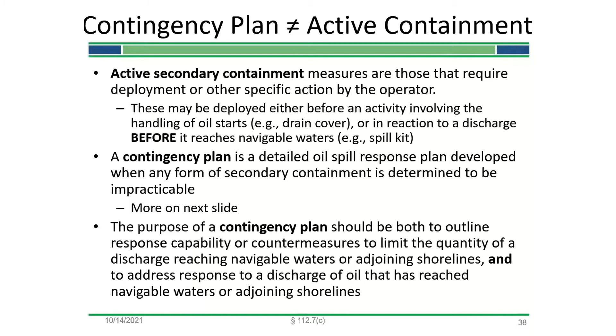Now, in some cases, it may be impracticable to provide secondary containment by any reasonable method. In these cases, the owner-operator may substitute a combination of other measures in place of secondary containment. So this is an impracticability provision, not environmental equivalence. Considerations for impracticability include space limitations, local ordinances or fire code, safety, or other good engineering practices. Economic cost can be considered, but it cannot be the only factor.